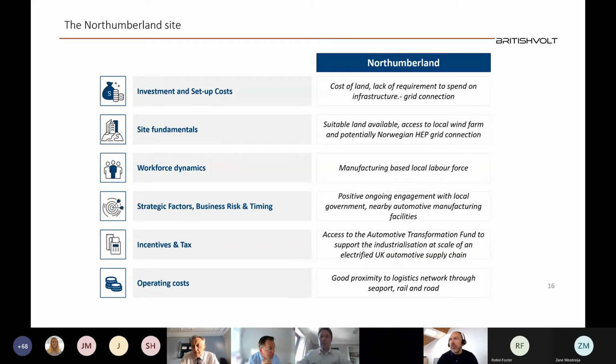There's big savings to be made if you get a direct national grid, non-DNO connection. And typically, if you ring up and you ask for one of 150 MVA, probably the phone goes quiet or some giggling at the other end, because it's such a massive, massive thing you're asking for. Once you actually get their attention, you're looking probably at 4 or 5 years, 50, 60 million pounds to get that grid upgrade done and in place.